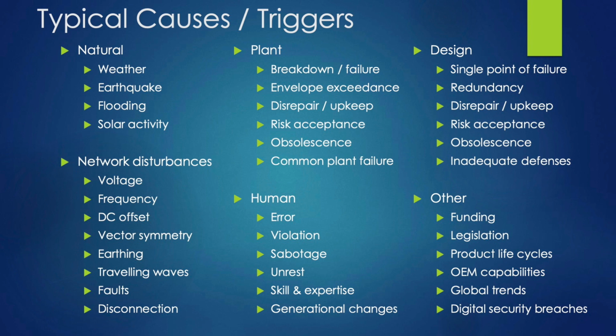Then there are design mistakes you can make, you can design a single point of failure type system. Silly, but amazingly, when we investigate it, we often find this, despite the fact engineers know to avoid it, and despite designs being reviewed and vetted, it's overlooked. Redundancy, disrepair and upkeep, a big one at the moment. Obsolescence, always an issue, oh I've duplicated obsolescence, sorry for that.